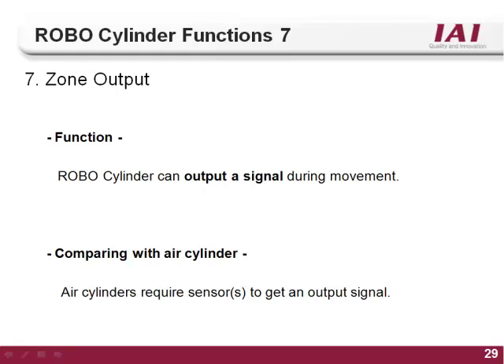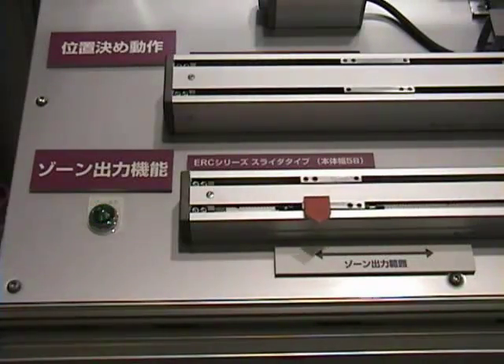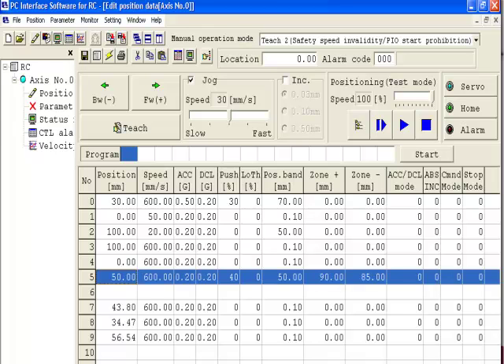The seventh and last function of the RoboCylinder controller is the zone output. With most air cylinders, reed switches are used to indicate actuator position information. Because all RoboCylinder actuators use encoder technology, there is no need for external switches. A zone can be set up anywhere on the stroke of the actuator — when the actuator moves into the zone, an output will turn on. The zone can be as small as the repeatability of the actuator or as large as the entire stroke. There are two types: the global zone, set inside the parameter file, which turns on the zone 1 output whenever the actuator is within the set zone regardless of what it is doing; and the position specific zone, set in the position table, where the P zone output only turns on when commanded to the position that zone is taught to.